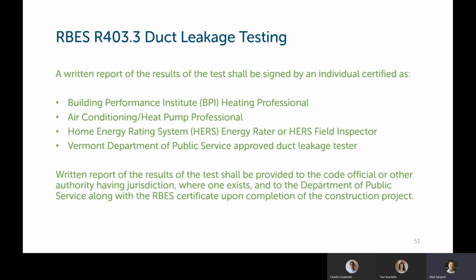So the duct leakage testing, we have to provide a written report. The person doing the testing and writing the report has to be certified as either a BPI heating professional, air conditioning or heat pump professional, a home energy rater, or the Vermont Department of Public Service approved duct leakage tester. So again, you have to file the report with the authority having jurisdiction. Also have to file it to the DPS at the state along with the RBES certificate.